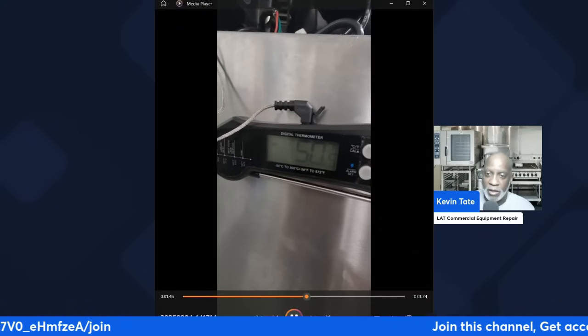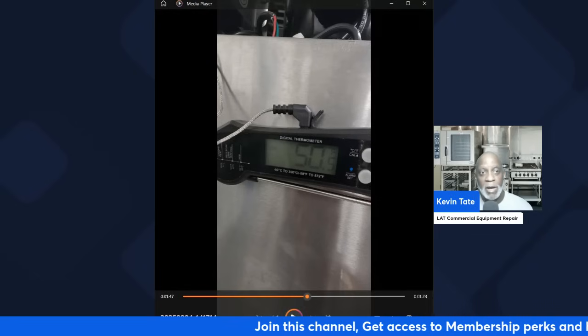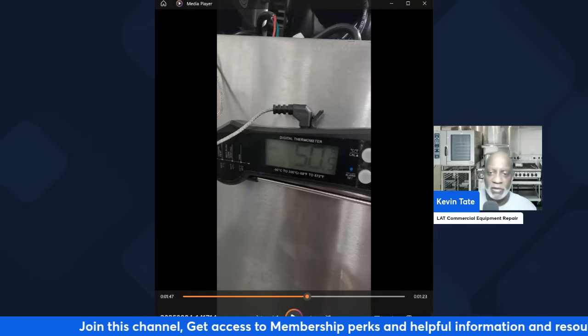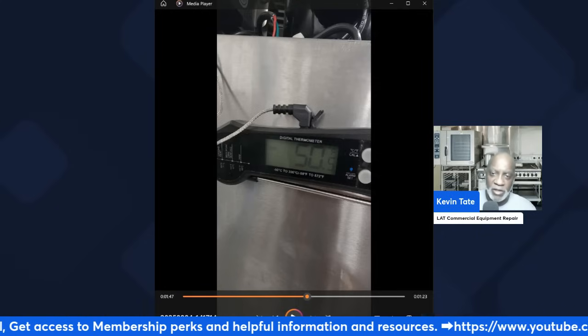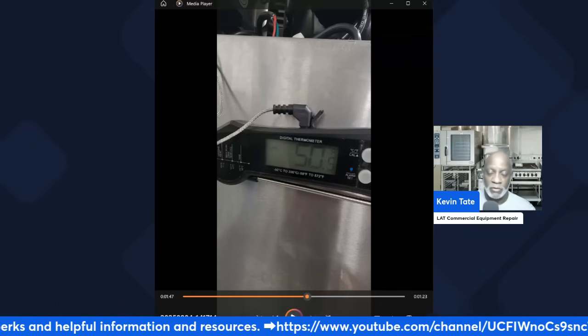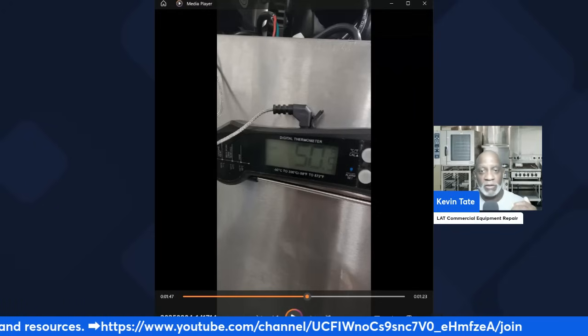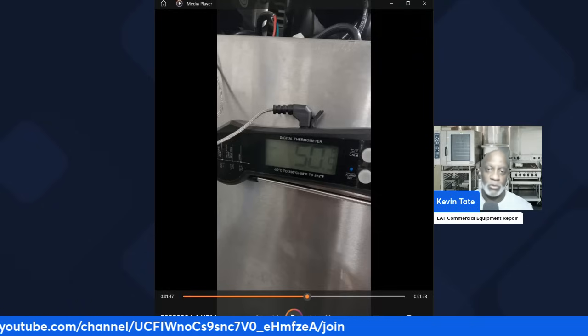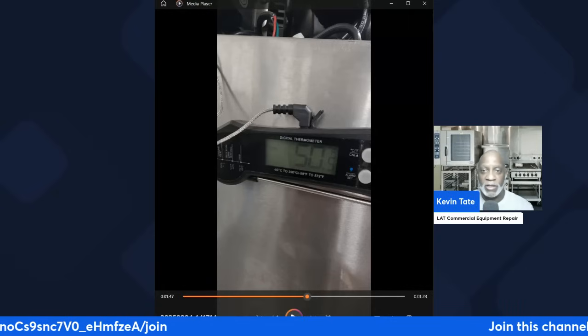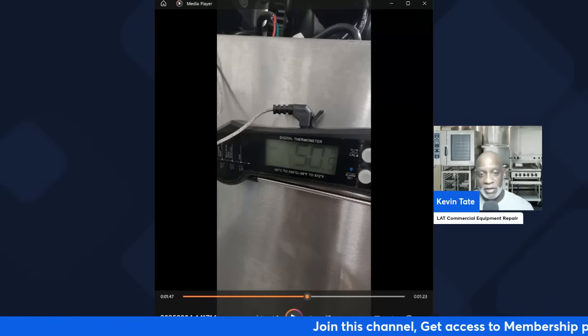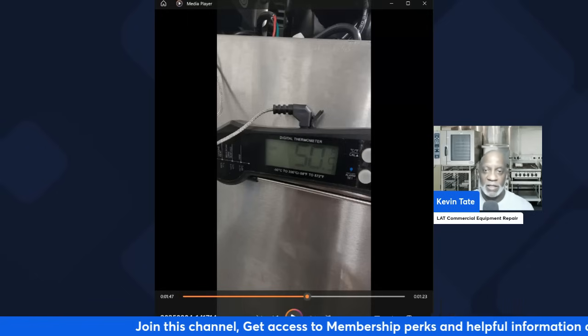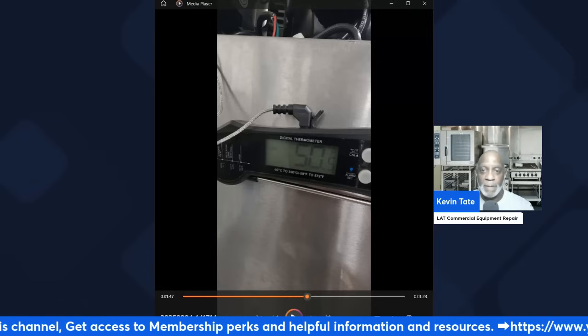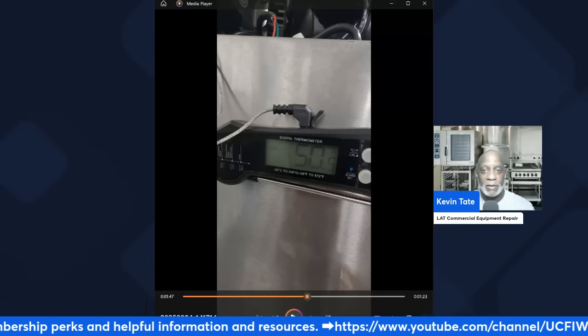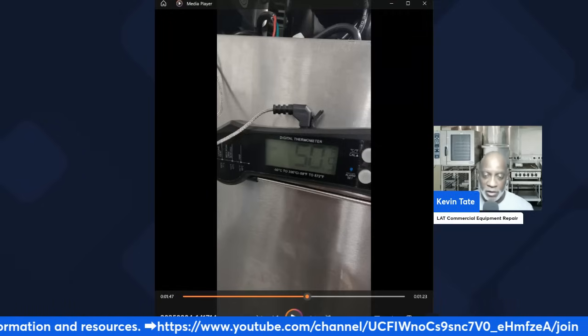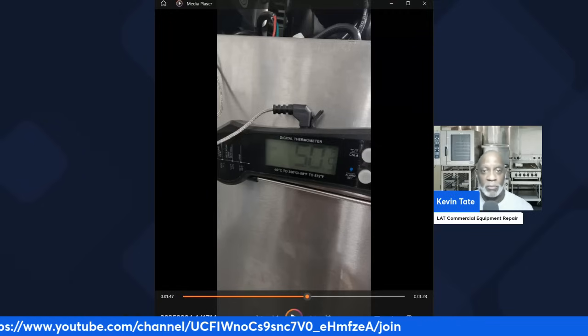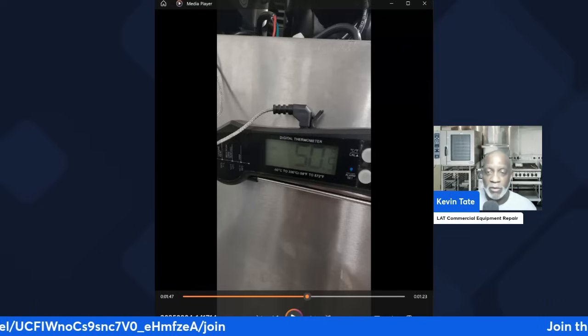Right now my temperature is 50. When I put my thermometer in, it was around 65, 66 degrees. So it's going down, and it's got to have time to freeze. While I'm waiting for it to freeze down, I'm doing other things. This is just an example of how you can do multiple things on a job and not take that long, because while this is freezing down, I can go ahead and clean and sanitize the bar gun, clean the condenser coil in the back, and empty the water out of the air compressor if it's using one. Some of these do not use it, but many do.